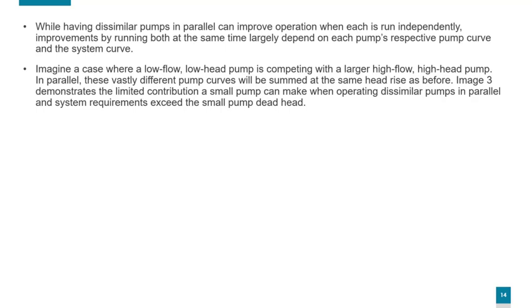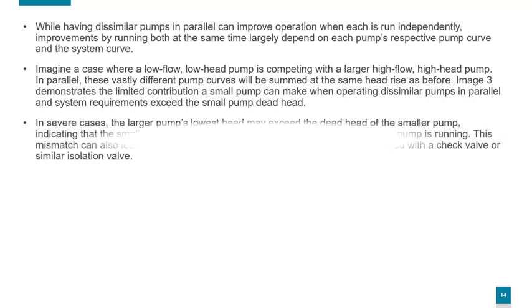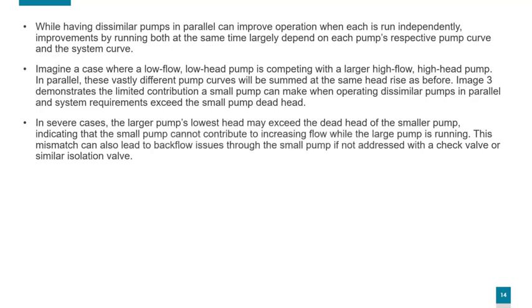The contribution a small pump can make is limited when operating dissimilar pumps in parallel and system requirements exceed the small pump deadhead. In severe cases, the large pump's lowest head may exceed the deadhead of the smaller pump, indicating that the small pump cannot contribute to increasing flow while the large pump is running. This mismatch can also lead to backflow issues through the small pump if not addressed with a check valve or similar isolation valve.